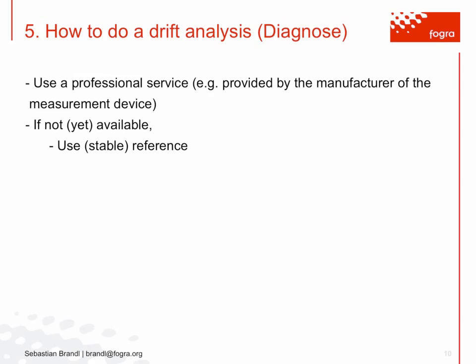Of course, use a stable reference as described, and at the minimum, we recommend to use the white tile which comes with the device. This is mostly doable, and mostly you can measure the white tile as you would measure a simple patch. For some devices, the white tile is kind of included and you can't use this as an external reference, but for most of the devices, this is doable.